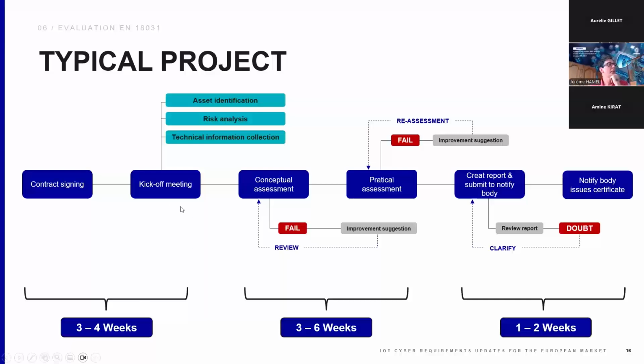So the first point is really to work on this risk analysis, asset identification, to collect all the information coming from everywhere related to the product implementation. Then to perform the conceptual assessment, via the filling of the Excel file or the web interfaces. Then it is evaluated by the lab. Then there is a practical assessment, which is a functional assessment. And also there could be some fails at this point. Then a report is created. So this is the report that should be used either for self-assessment or to issue a type examination certificate as a notified body.